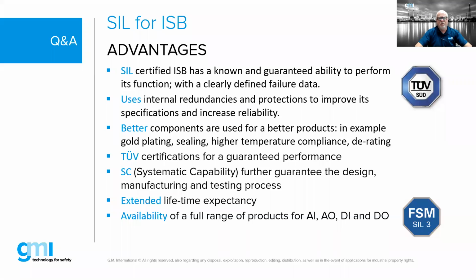In order to achieve a SIL rating on a particular component, whether it's a valve, an intrinsically safe barrier, a PLC or whatever it is, there has to be a tremendous amount of traceability of all the individual components, and there have to be calculations of failure modes, when they are going to fail, all of this documentation. So when you build an intrinsically safe barrier that has a SIL rating, everything that goes inside of that barrier has gone through a significant amount of data and testing to determine how this product will operate over a long period of time. In effect, what you're paying for in this scenario is reliability.